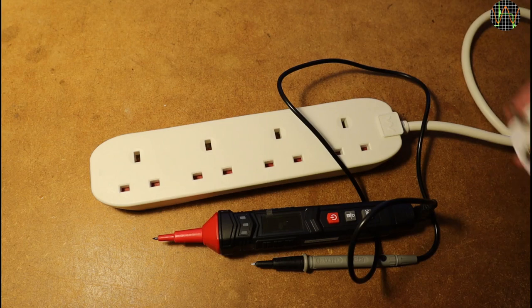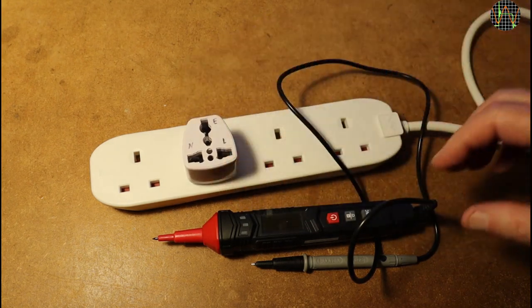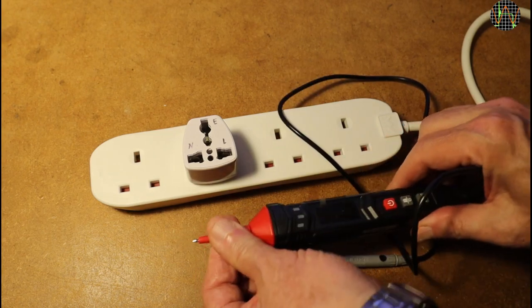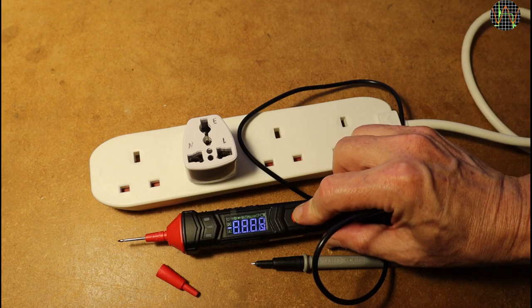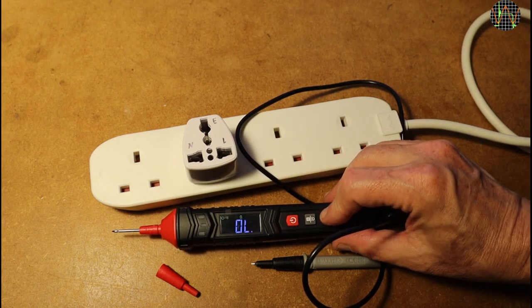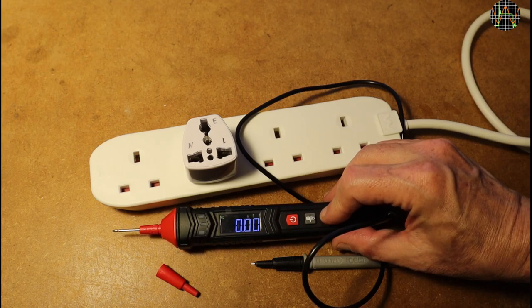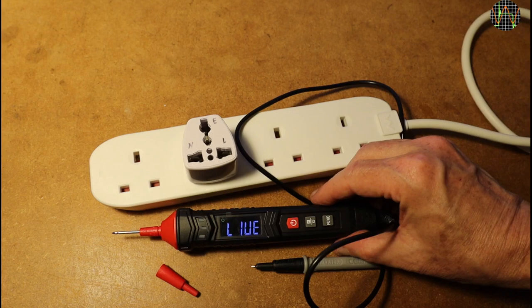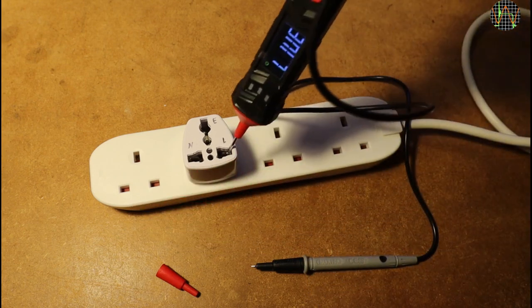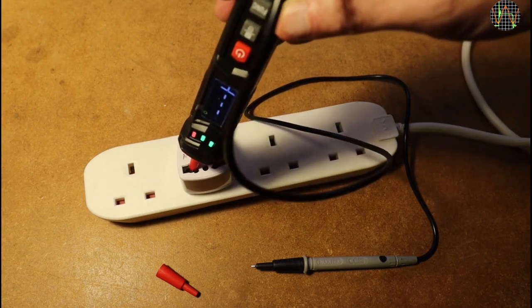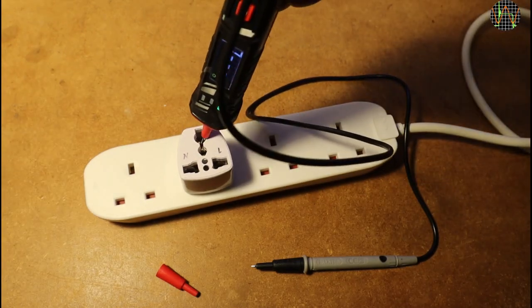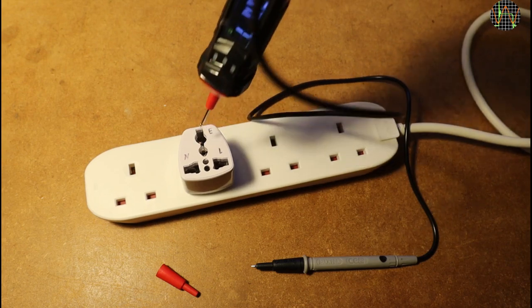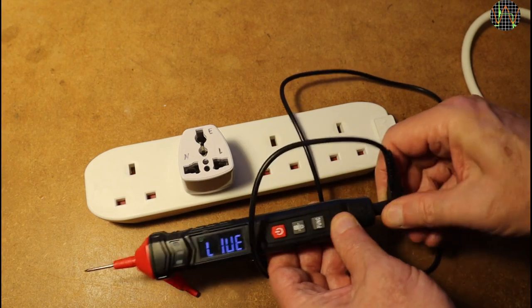For a quick check of the detection of live voltages, I used this adapter to make accessing the UK power sockets easier because they are normally closed by shutters where no plug is inserted. For this test, it is important not to plug the black lead into the ST120. First of all, it is a safety issue. You can see that the ST120 becomes way too sensitive and detects live voltages everywhere, even on neutral and on earth, rendering this function useless.